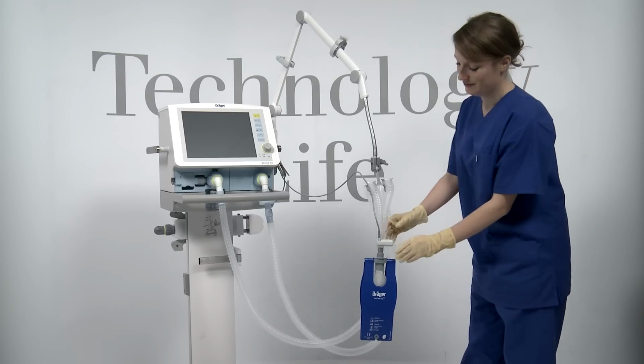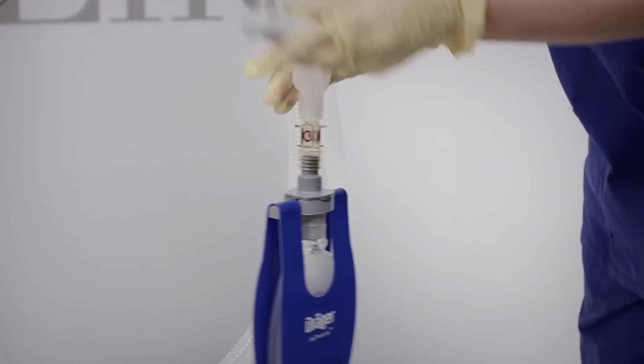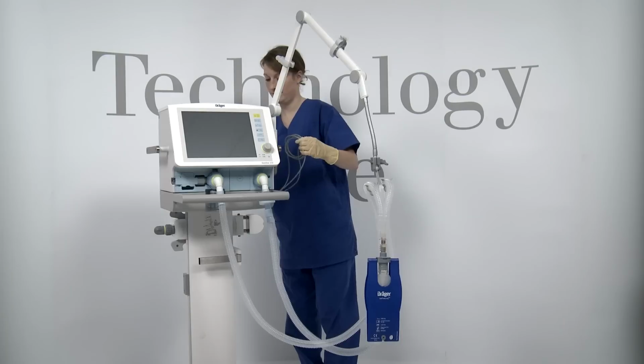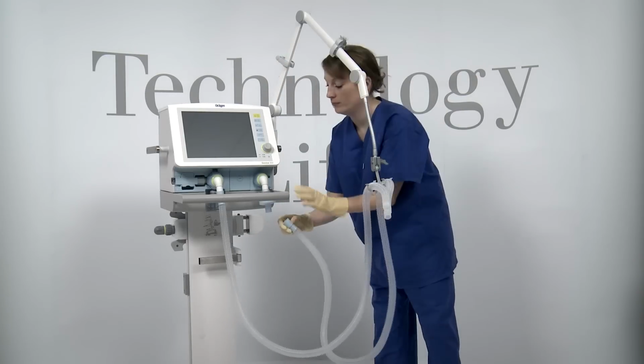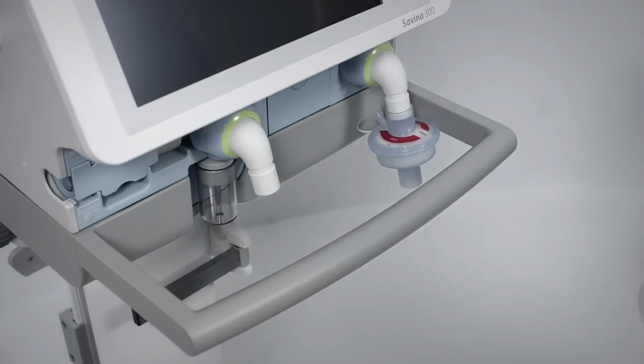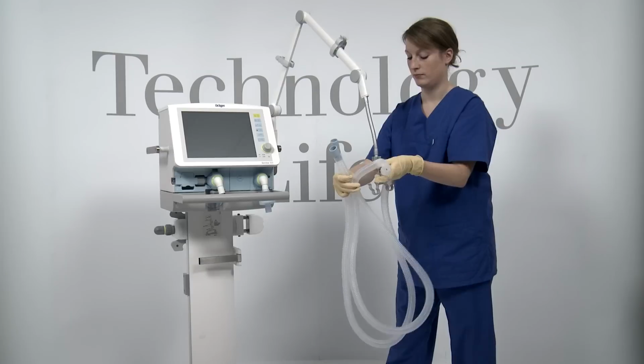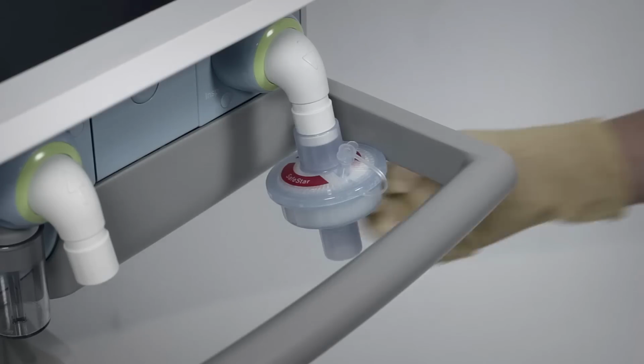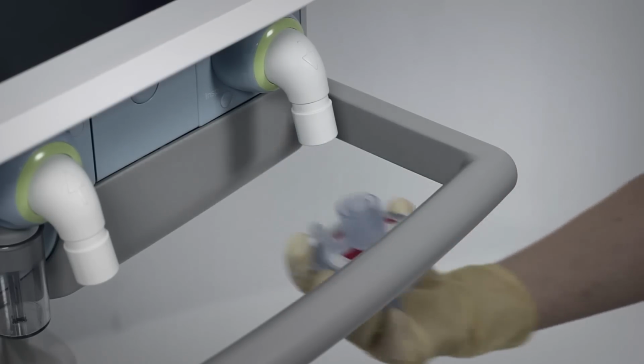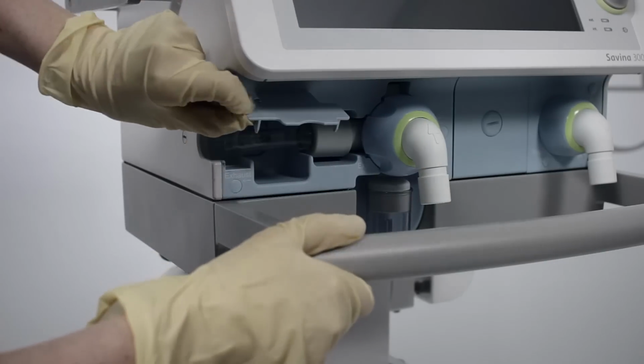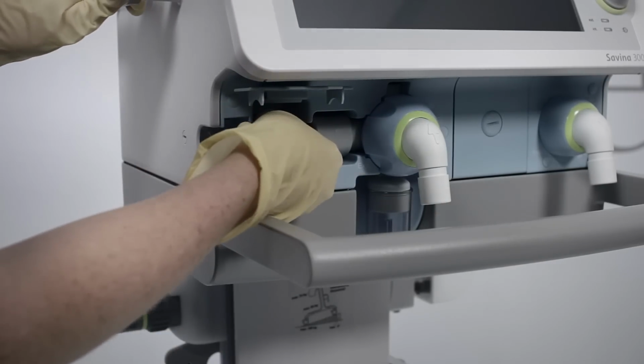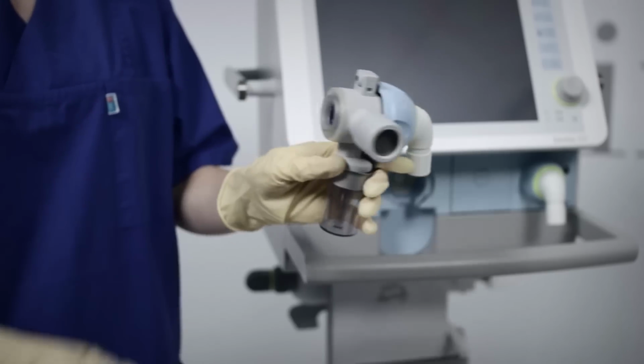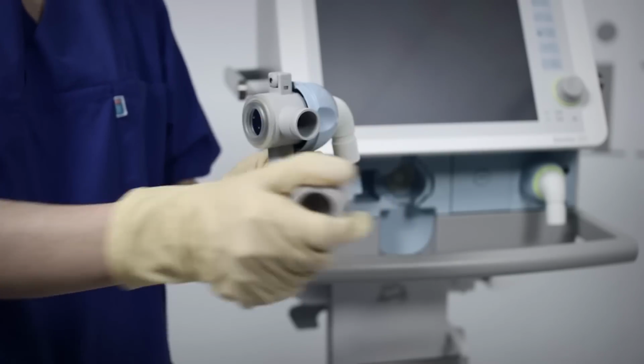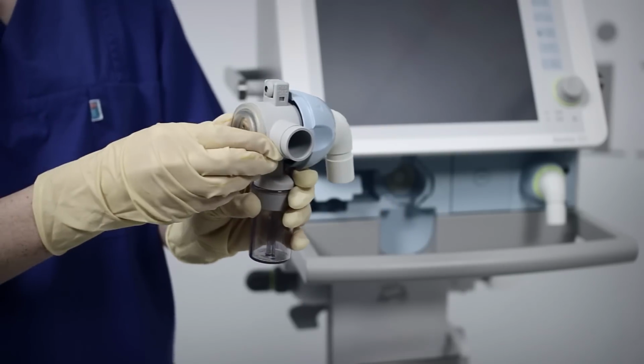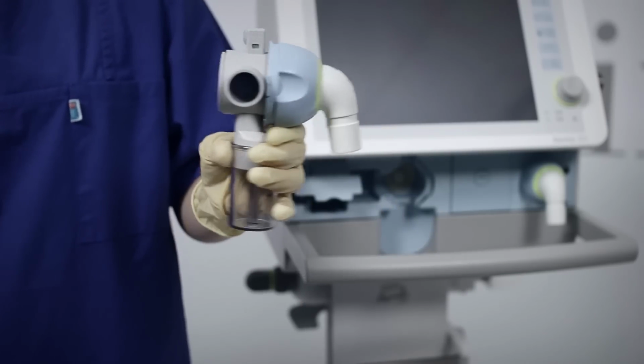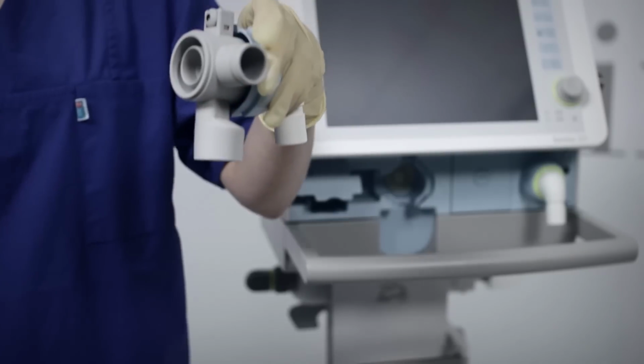Now remove the CO2 sensor. Please note that only reusable cuvettes and sensors can be reprocessed. The breathing hoses. The bacterial filter. The flow sensor. The expiratory valve. Pull the flow sensor sleeve from the expiratory valve and remove the diaphragm. Remove and empty the water trap container.